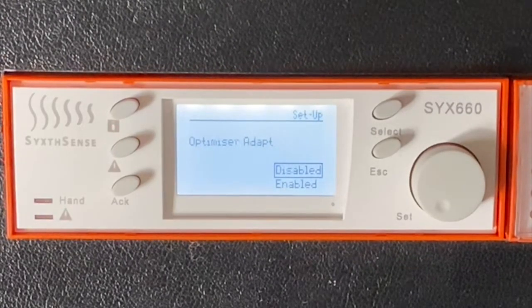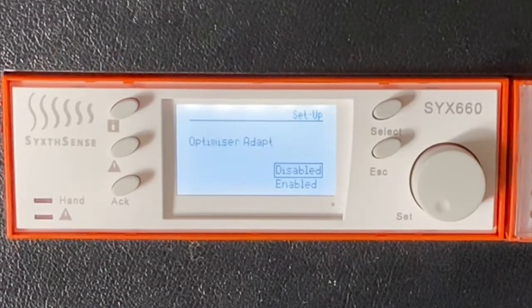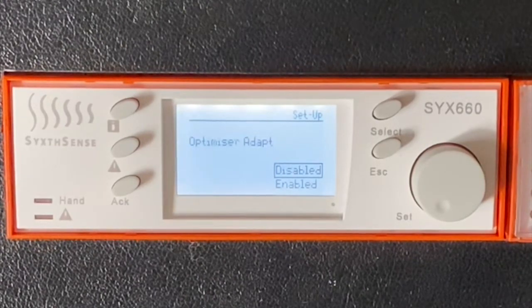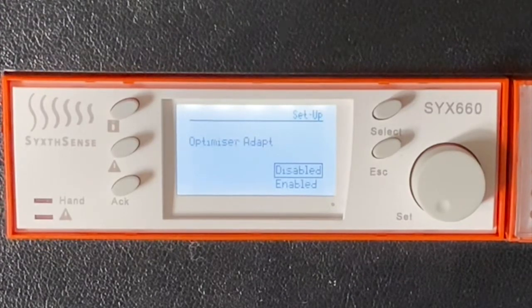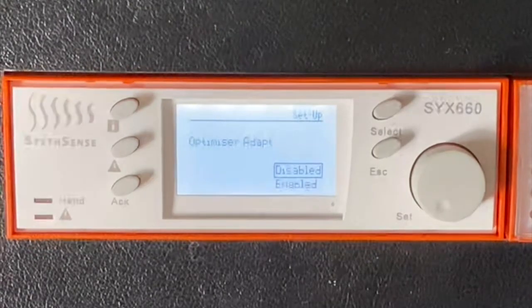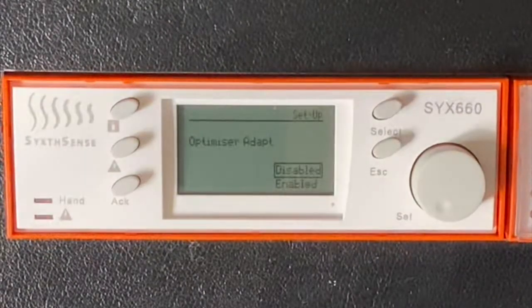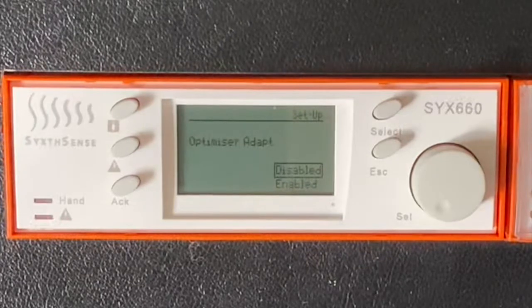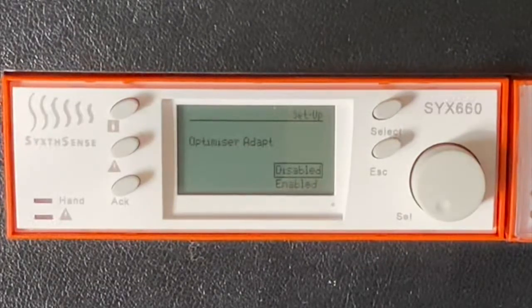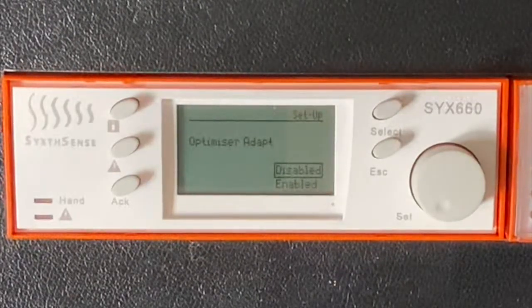This is a very important factor which we should understand about the controller, because this is essentially showing us how efficient the building is, and it's also showing us how the current heating plant is performing within the building. So we end up with a sensible relationship between the heat supply and the building efficiency, so we can see how buildings compare with each other on a day-to-day basis, and also seasonality as well has a massive effect.